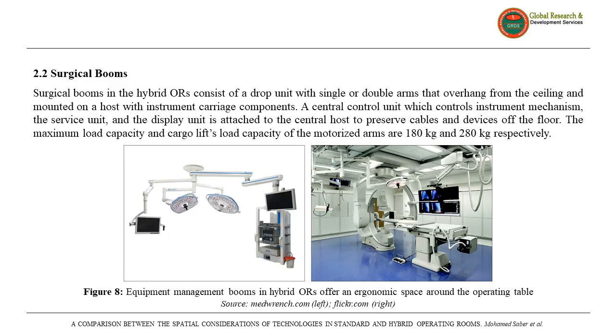Surgical booms in the hybrid operating rooms consist of a drop unit with single or double arms that overhangs from the ceiling and mounted on a host with instrument carriage components. The central control unit, which controls instrument mechanism, the service unit, and the display unit, is attached to the central host to preserve cables and devices off the floor.